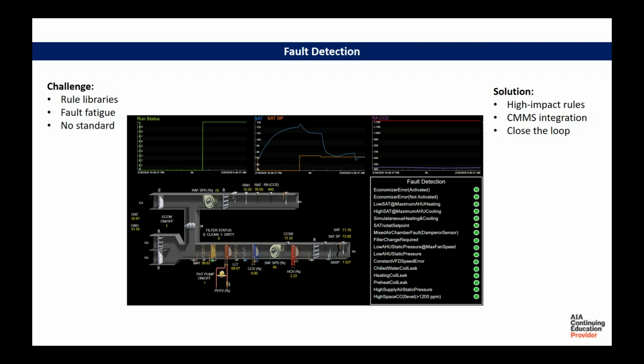One example, again looking at an air handler like this, would be comparing your supply air temperature versus your supply air temperature set point and having a fault if there's a 2-degree deviation, so if you're more than 2 degrees away from that set point. That's a rule that's in a lot of systems. It's a rule that was in a system I've worked on. And you really have to step back and ask, is it valuable?